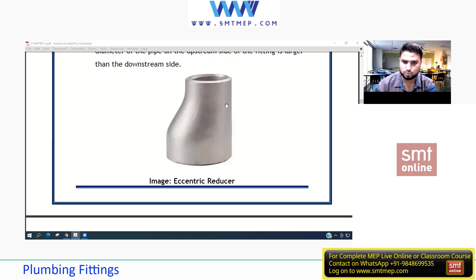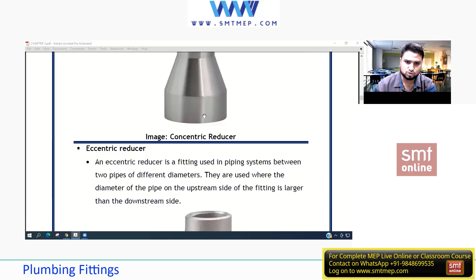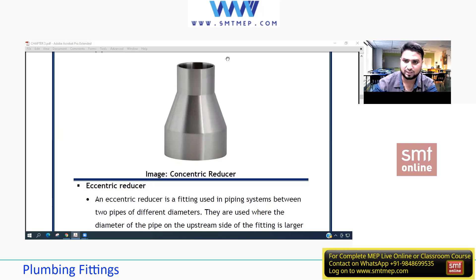Exactly, a chilled water pipe or nearby the pump. The reason is that in the suction side, this reducer is installed. If you see the suction side, with a normal reducer the shape creates a shift, it's not flat, so it might create air bubbles or an air gap. Second, cavitation will be forming. To avoid that cavitation and the air gaps, we use this kind of reducer there, so always in the suction side the water goes in this manner. This is used nearby the pumping system or connected to pumps. In the suction side, remember, because of this shape, the water touches the surface directly and there is no gap between the material and the flow, so no air gaps and no air bubbles.